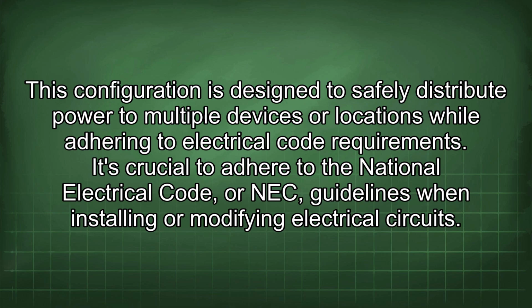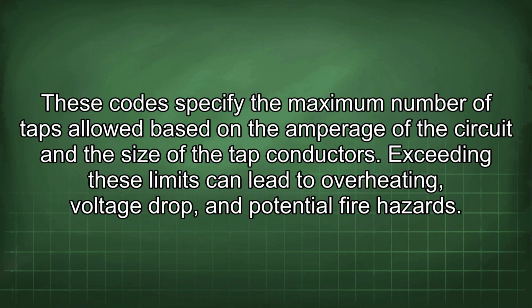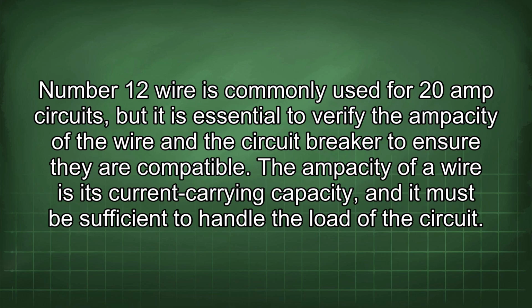electrical code requirements. It's crucial to adhere to the National Electrical Code, or NEC, guidelines when installing or modifying electrical circuits. These codes specify the maximum number of taps allowed based on the amperage of the circuit and the size of the tap conductors. Exceeding these limits can lead to overheating, voltage drop, and potential fire hazards. Number 12 wire is commonly used for 20 amp circuits, but it is essential to verify the ampacity of the wire and the circuit breaker to ensure they are compatible.